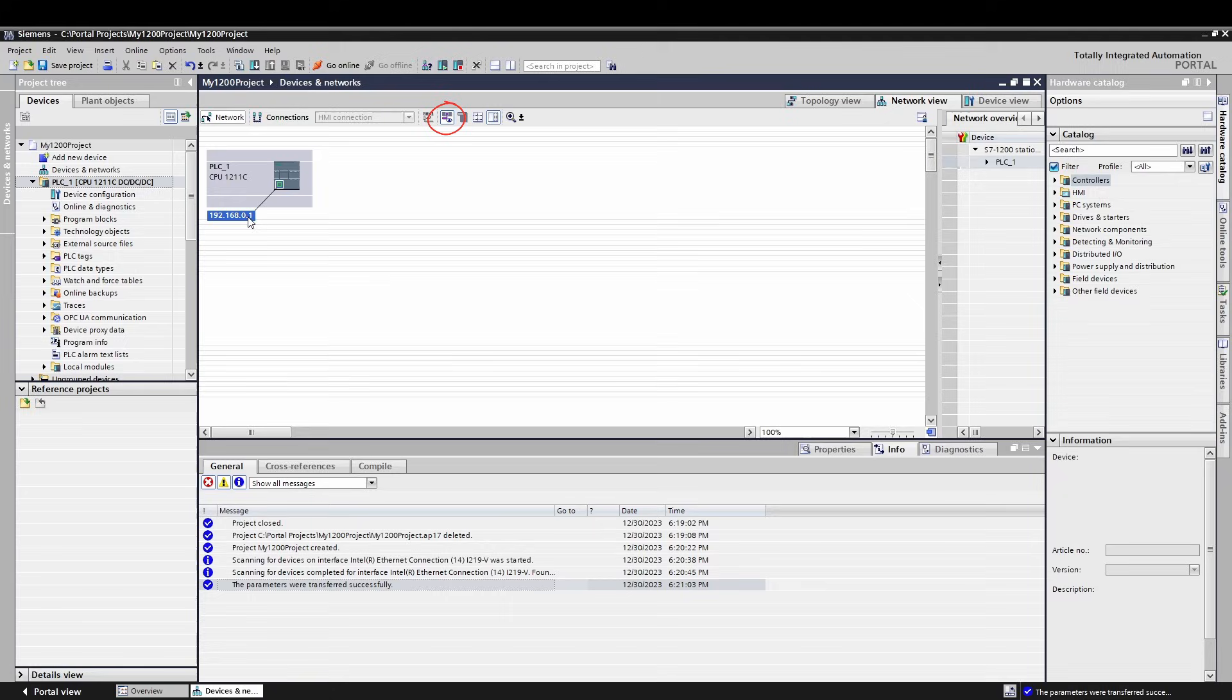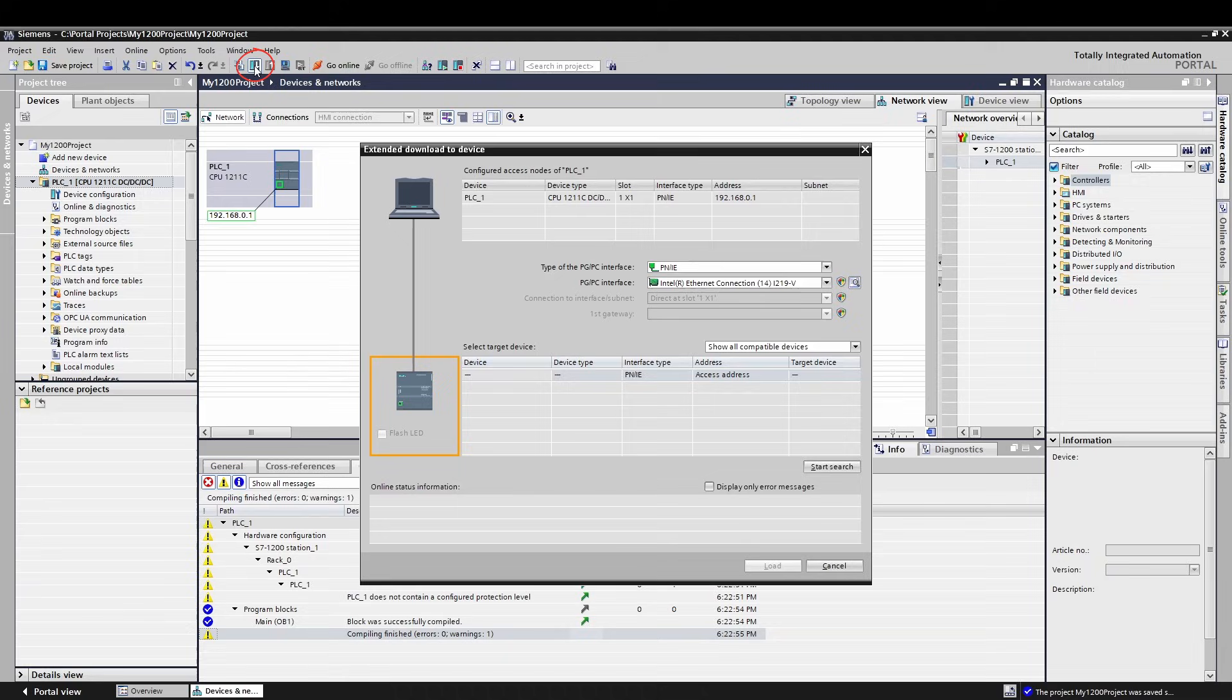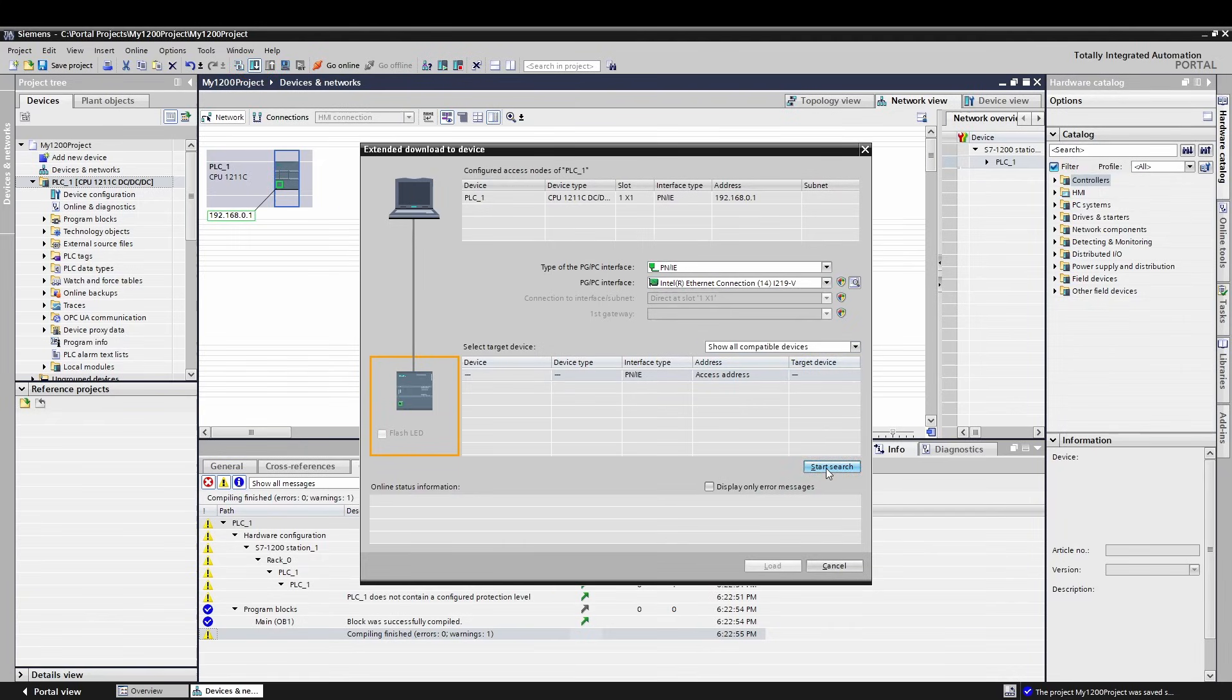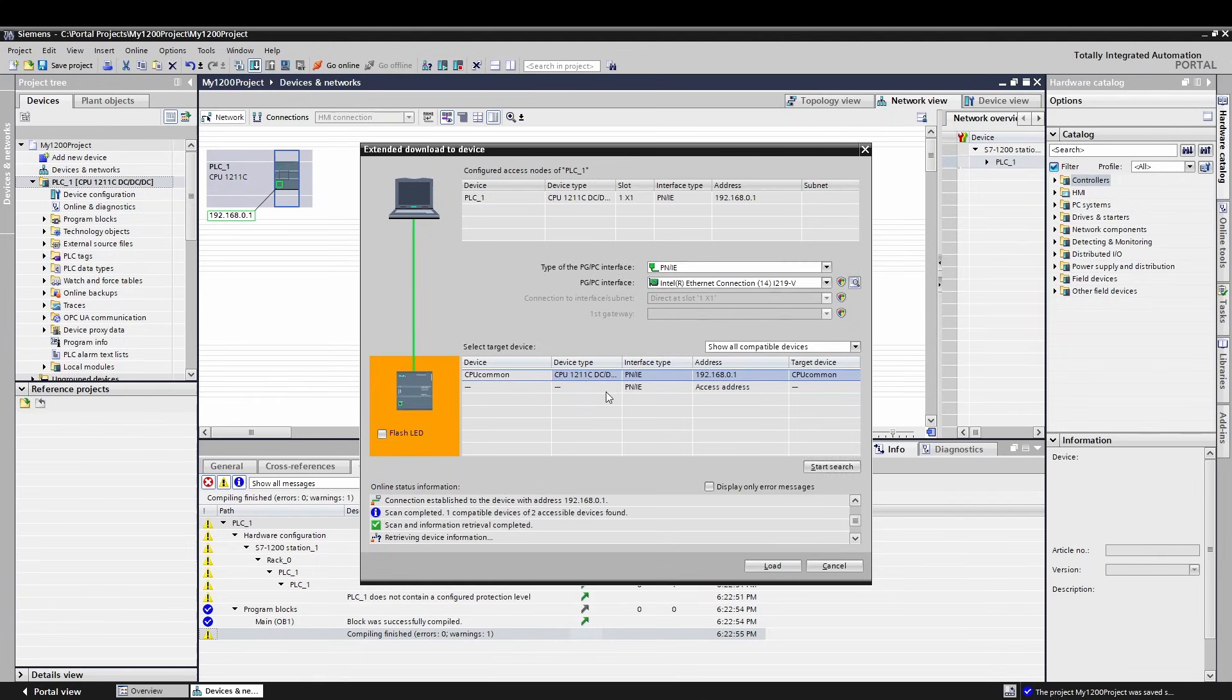Since we took the time to set the IP address on the PLC beforehand, we just need to change the IP address in our project. Click the View Addresses button at the top of the Network View. Note there are three views on this same screen. If you don't see this button, check to make sure you are not in the Device or Topology view. They are important to know how to use, but not for this video. Change the IP address to the address you set before, or you wrote down earlier. Select the PLC and press the Download button on the main toolbar.